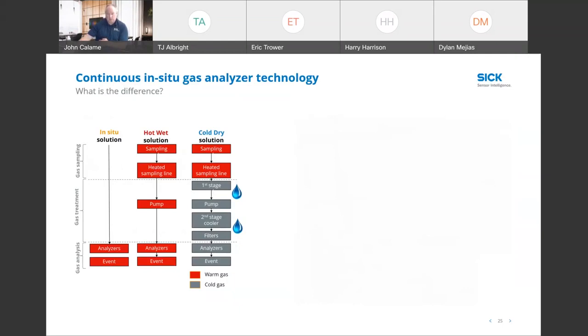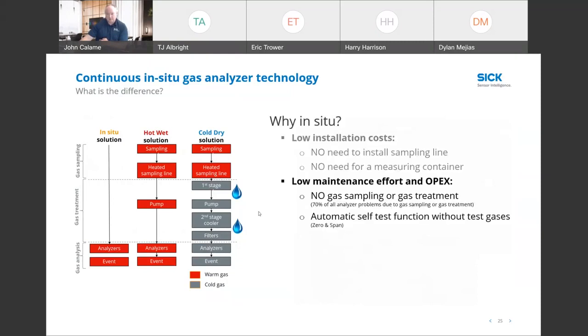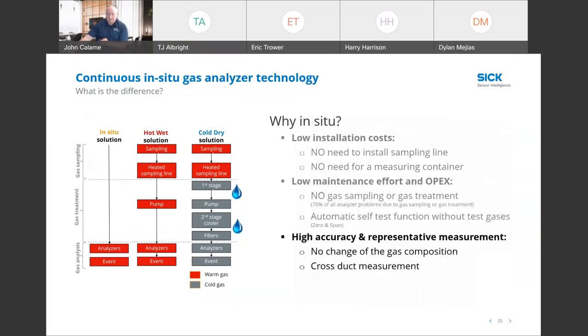All have their pros and cons. The cold dry has more components here because we're doing extraction, we're doing cooling and dropping out moisture, and have a lot of filters. So there's a lot more components that are involved in that. And the best thing about the direct in situ measurement for controlling and optimizing is the speed of response, being in the process rather than having an extracted sample and dealing with maybe the sample delivery time, delay time. Dylan, anything you wanted to add to that?